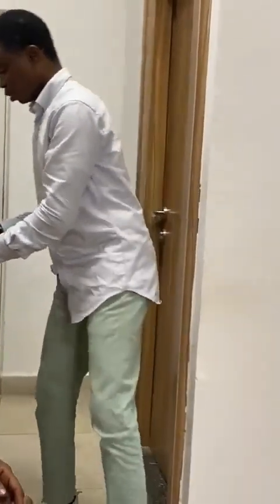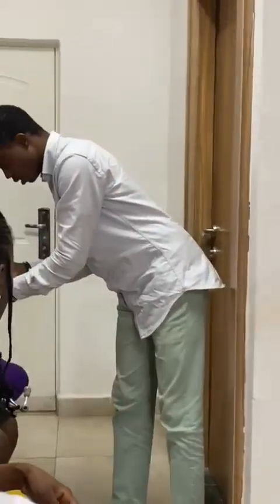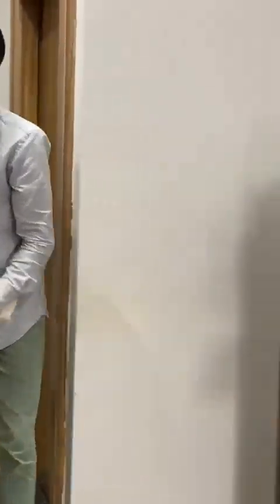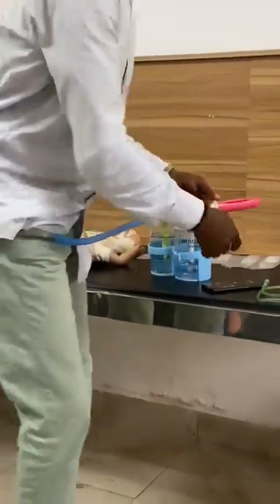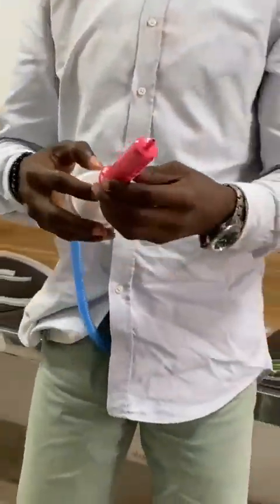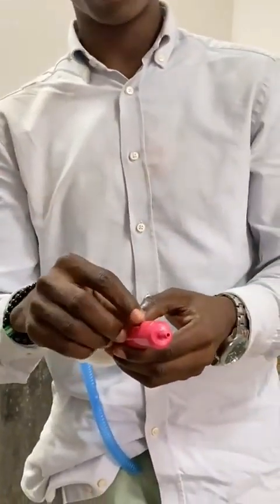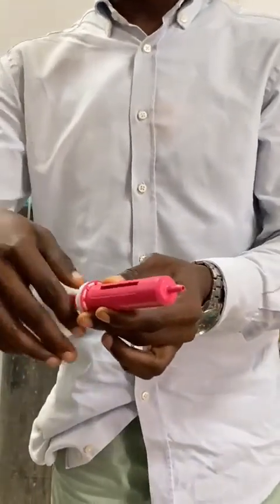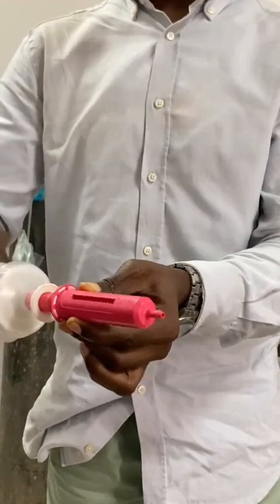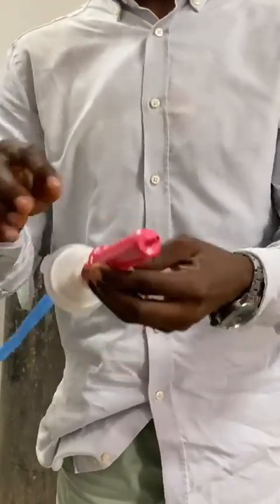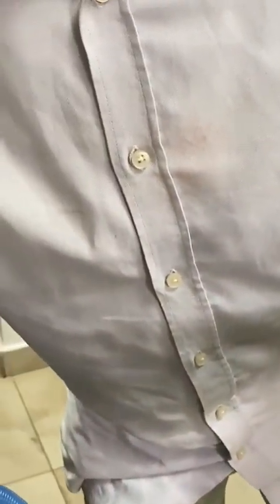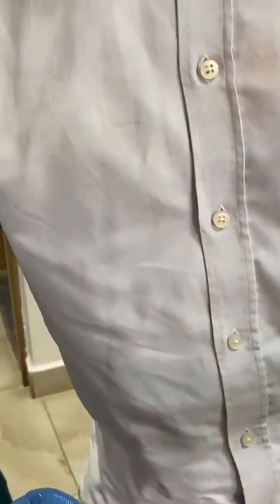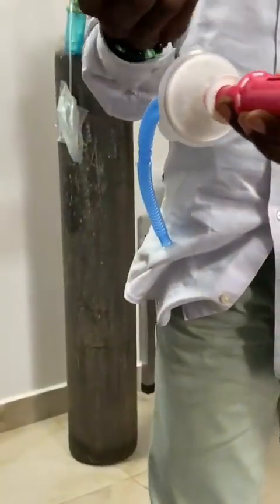So it's showing you the calibrations, the prescribed setting. It depends, and you know the FiO2 is based on the patient's requirement. So for you to adjust to a desired FiO2, there's a last thread. How you do it, just reduce this to make it open, then you can adjust. So wherever the last, let's say this is, now you can see this 80. This one is the one that determines where you set it. So you are administering at an FiO2 of 80% oxygen.